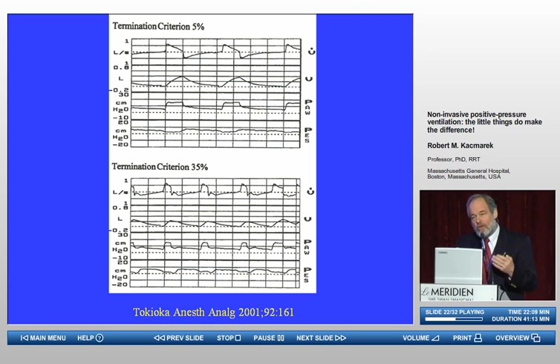So it almost looks like there are two breaths being administered. And as you'll note in this example, decreasing the termination criteria to 5% totally eliminated those issues on the airway pressure as well as on the flow curve. So I think it's a very useful adjunct to allowing you to customize that pressure support breath to the desires of the patient at a particular point in time.